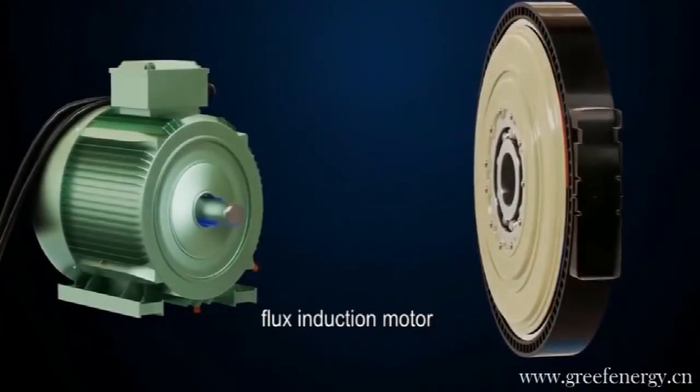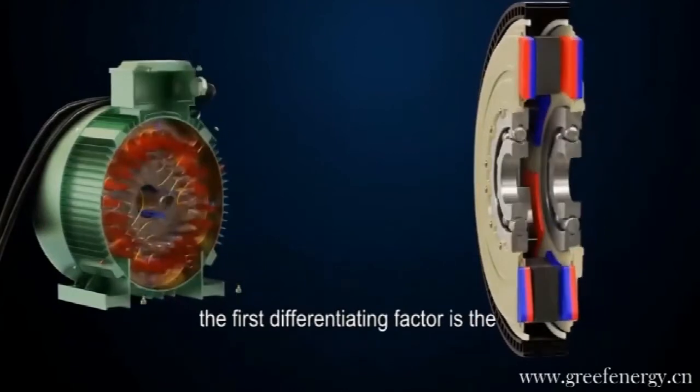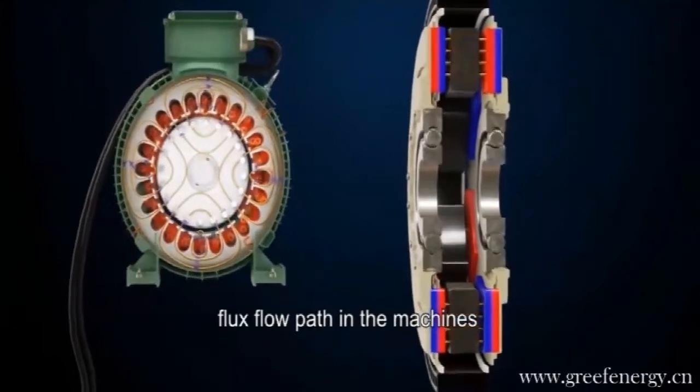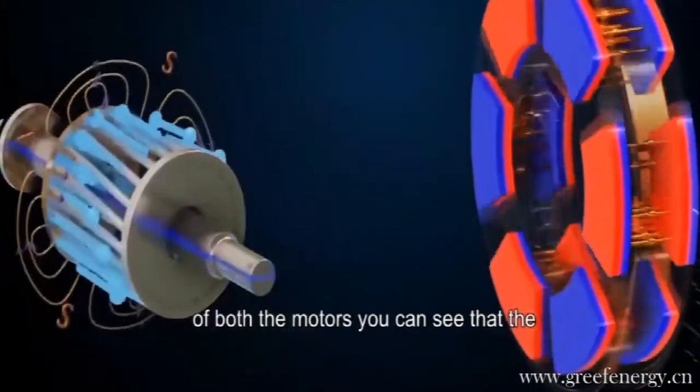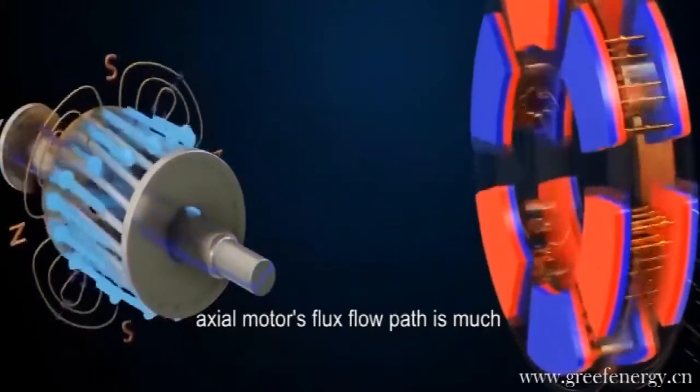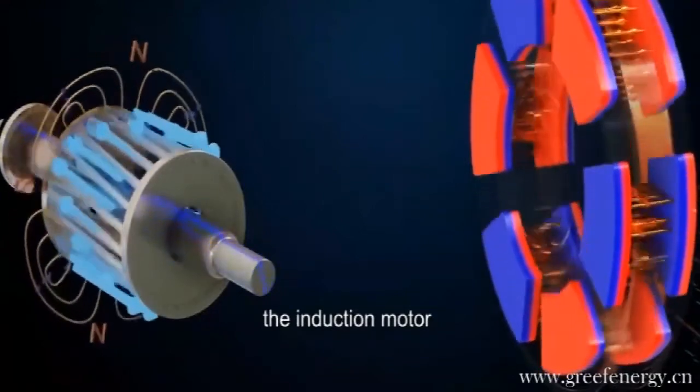Let's compare the axial flux motor with the most commonly used motor, the radial flux induction motor. The first differentiating factor is the flux flow path in the machines. If you compare the magnetic flux pattern of both the motors, you can see that the axial motor's flux flow path is much more dense and shorter when compared to the induction motor.